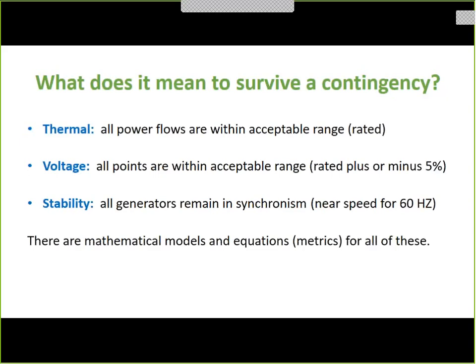What does it mean to survive a contingency? I said you have to survive it. It means that you have to check three things, usually. You got to check the thermal limits. Nothing can be overloaded. You're not burning up anything. Nothing is outside of an acceptable range. For example, the current has to be below a certain amount on every line. It could be a voltage problem.